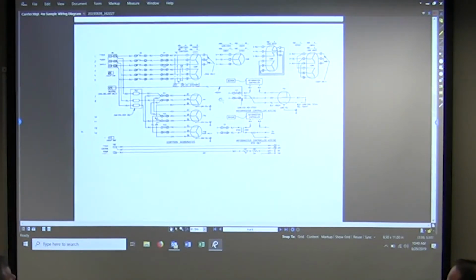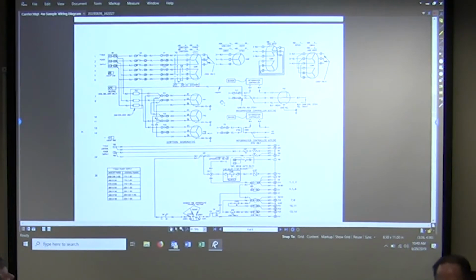Page 4, we now get into what looks to be our high voltage side of our unit. You can see I have 3 phases that feed into what looks to be a compressor, and how many stages or sections of that compressor are shown wired here? 2 stages, right? I got an upper section and a lower that show 3-phase wiring to it. So there are some options over to the right that could be wired in depending on the model. So if it's a single stage or single section or different types of wiring.